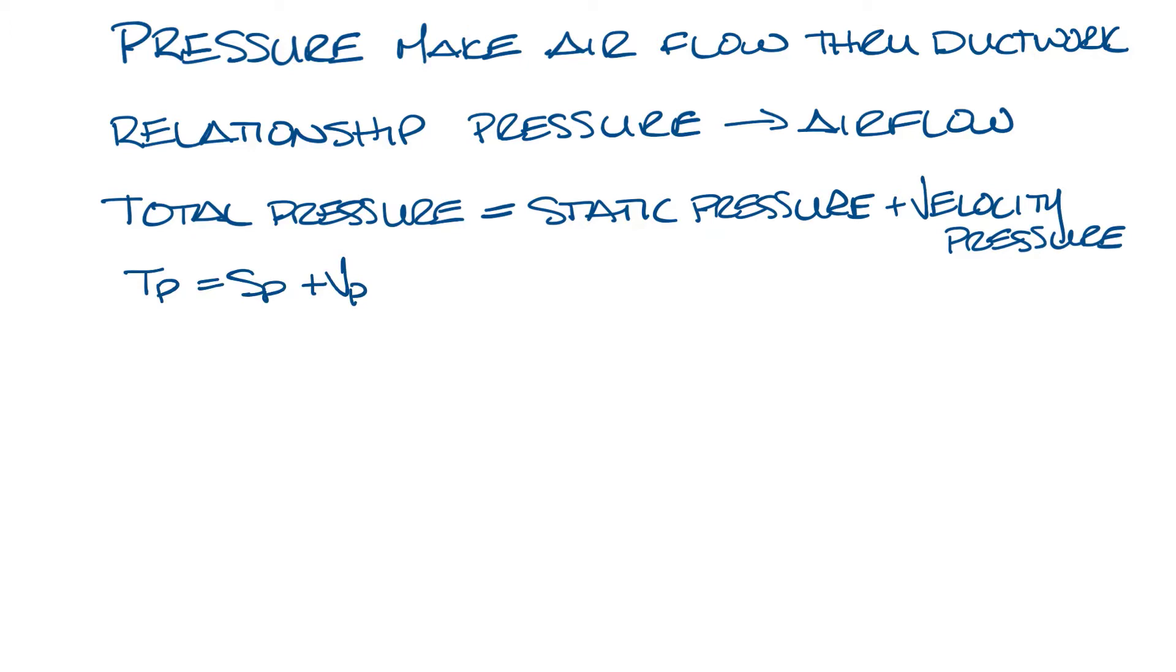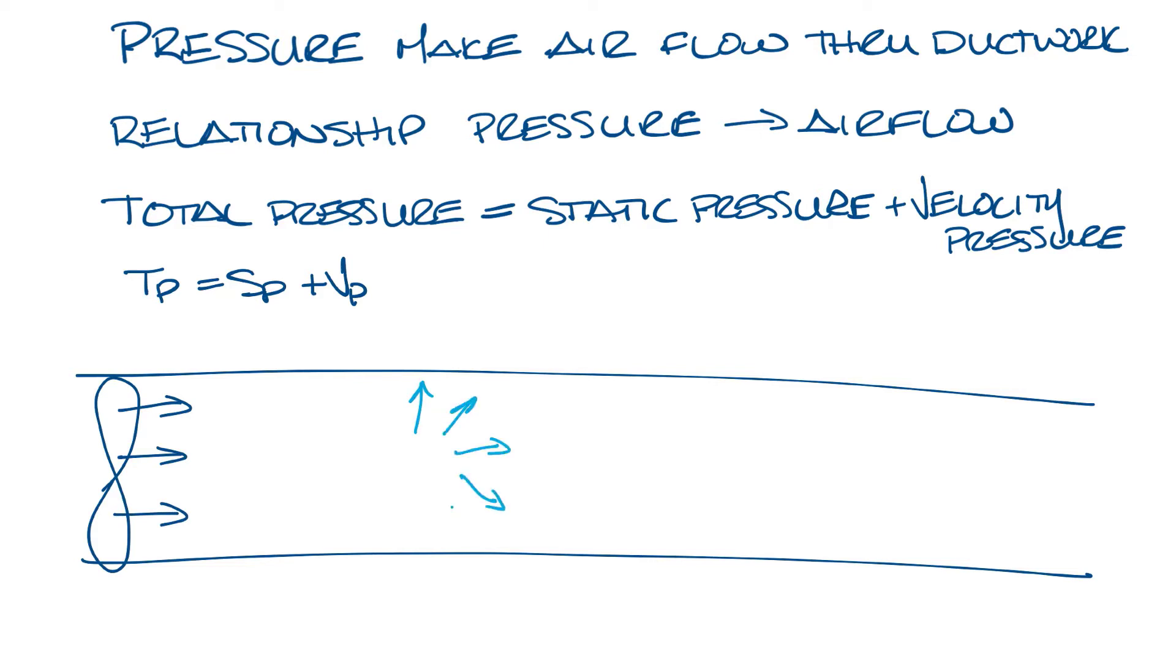So let's draw some ductwork and put a fan here blowing air down our ductwork. When air moves down the ductwork, there are two types of pressures going on. Static pressure, which is exerted in every direction, and velocity pressure, which is only exerted in the direction of air flow. The sum of these two pressures is total pressure.